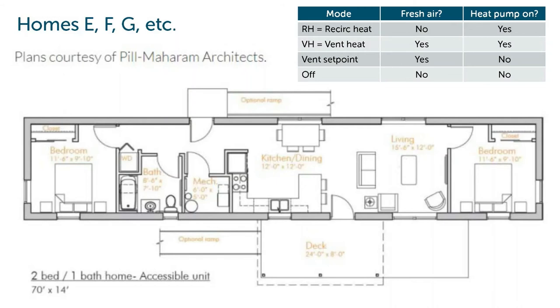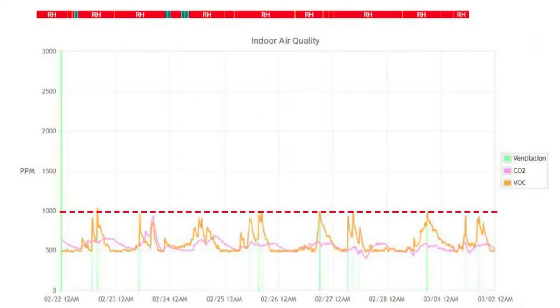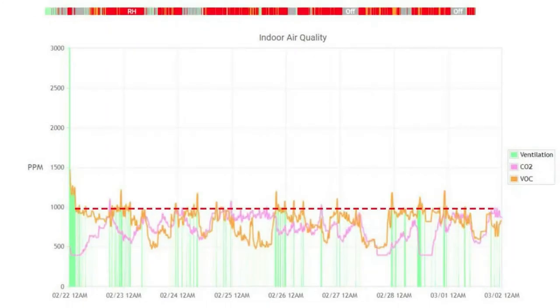The system has an integral heat pump with four modes of operation as shown in the table, and the drawing is representative of a typical ZIM layout. This chart shows 1 week of data for home E. As you can see, each time the CO2 sensors register 1000 ppm, the ventilation unit kicks on. Here's home F during the same week. This graph shows the VOCs also driving the ventilation system to kick on.